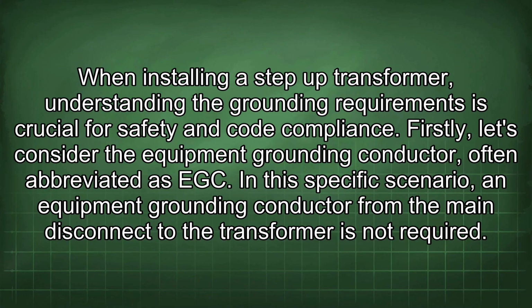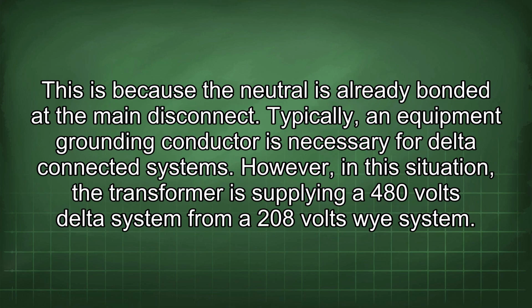When installing a step-up transformer, understanding the grounding requirements is crucial for safety and code compliance. Firstly, let's consider the equipment grounding conductor, often abbreviated as EGC. In this specific scenario, an equipment grounding conductor from the main disconnect to the transformer is not required. This is because the neutral is already bonded at the main disconnect.